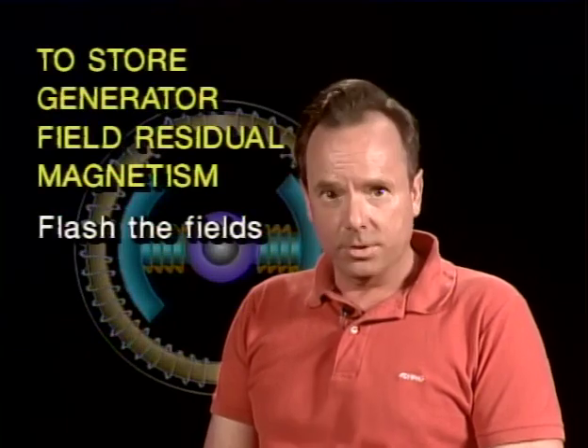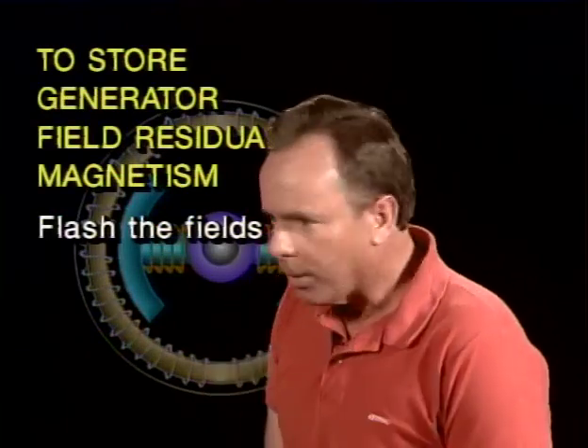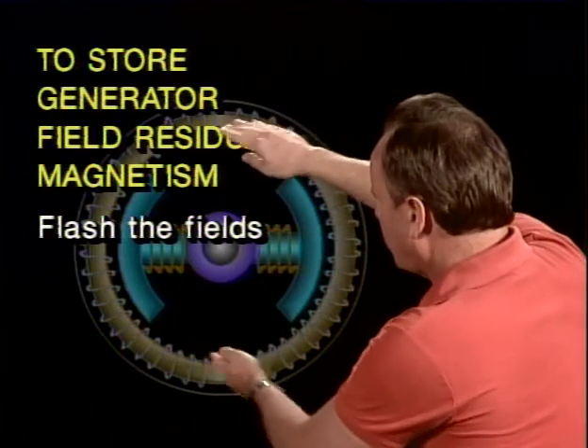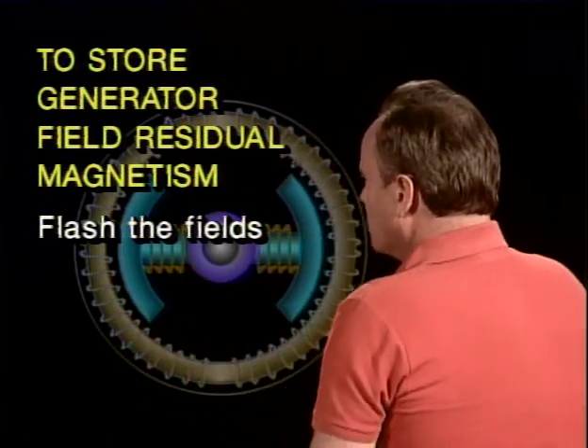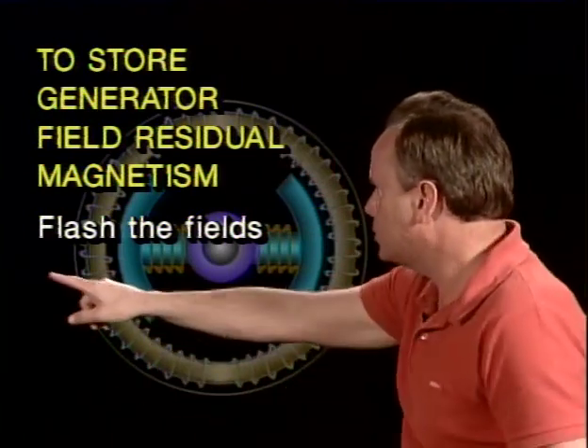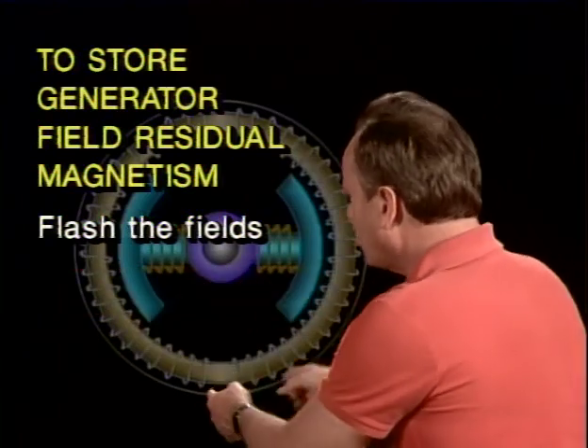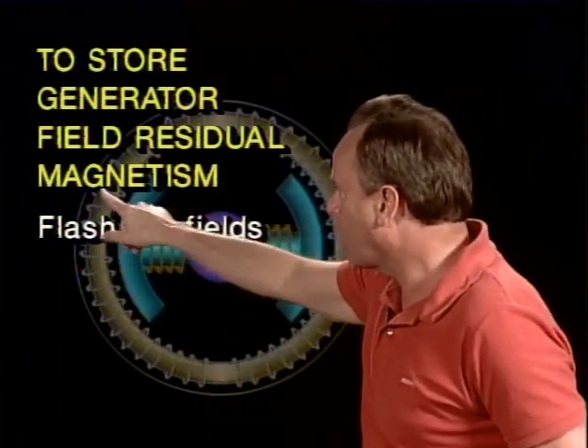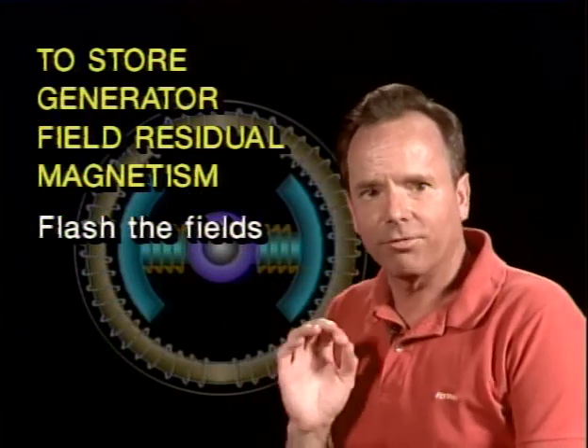Now, what is a method used to restore generator field residual magnetism? In other words, some residual magnetism in this field is useful and valuable. So if you want to restore it, what do you do? The answer is you flash the field. You put an electric current through the field, and that restores residual magnetism. So you can flash the fields, and that's another question they're going to ask you on the test.